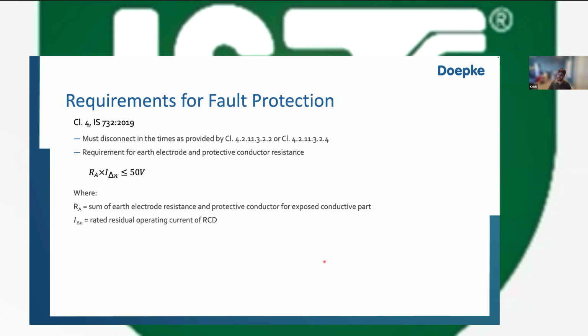The standard requires in clause 4, IS 732, that you must have disconnection in certain times provided in these clauses. This is generally 1 second, 5 seconds, 0.2 seconds, or 0.4 seconds. For an elevator, generally this time would be approximately either 1 second or 5 seconds, depending on the system. But for certain smaller elevators, it could even be 0.4 or 0.2 seconds. But in general, let's assume 1 second for a TT system, which is what is in this clause.